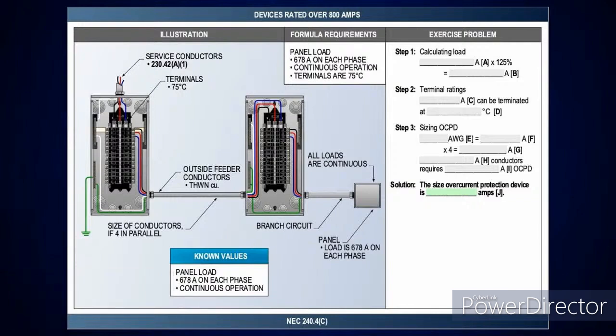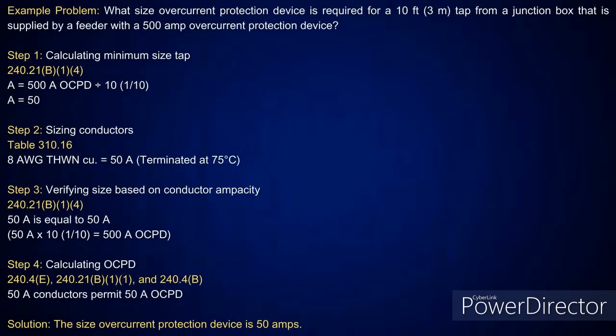Awesome. All right, and here's a feeder going over to a panel board. We're going to size it four times. The load's 678 amps. It's continuous and 75 degrees C terminals. So just take that 678 amps at 125% and start sizing your terminations based on Table 310.16 to get the total amperage, and then you can size your overcurrent protection device. Okay?